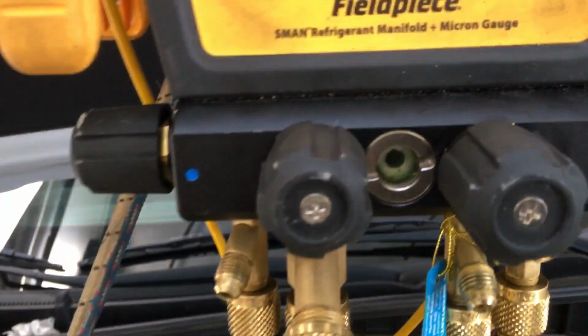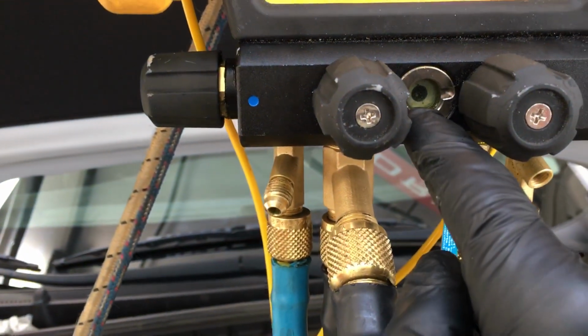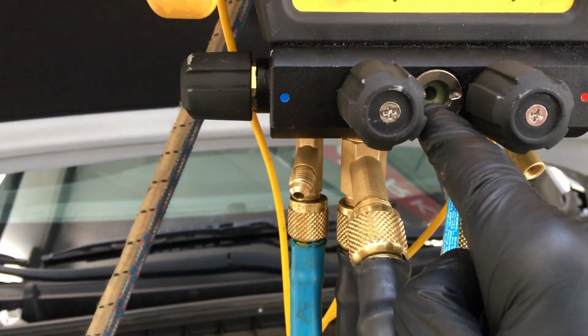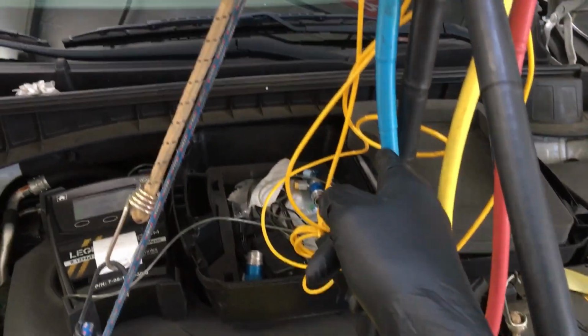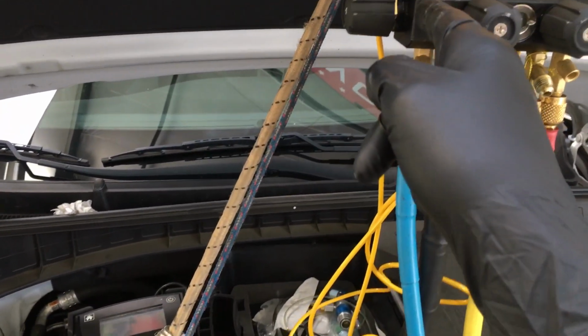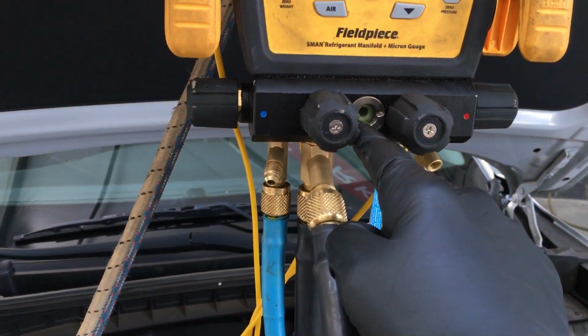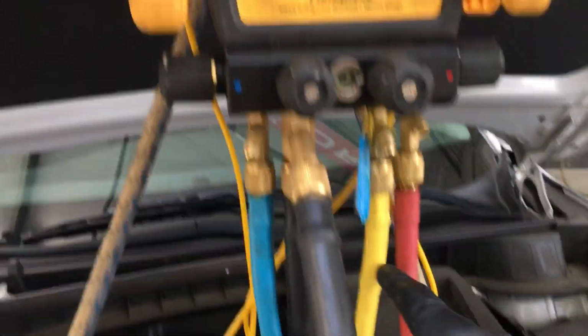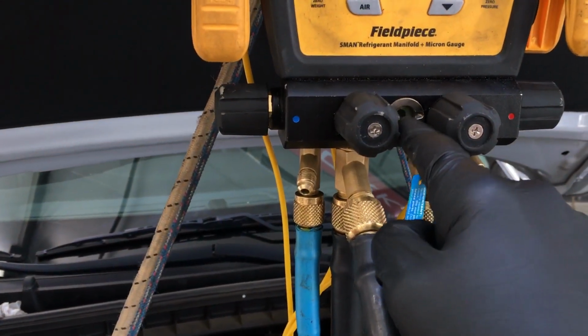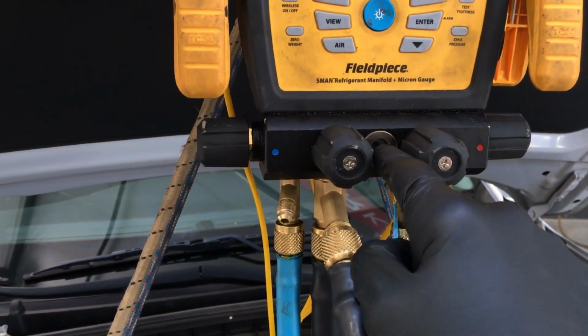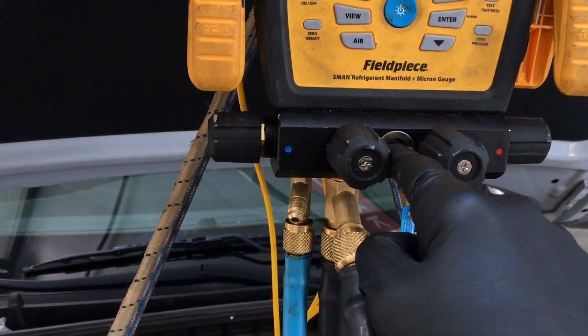That's one thing to remember: when you do recoveries with portable equipment, you always have to monitor—get your flashlight, look inside this little hole right here. When you start taking up refrigerant that's in vapor form, it has to pass the sight glass and then down to come here. What you do is look and make sure you're not pulling out liquid, because if you're pulling out liquid, you're pulling out oil with it.